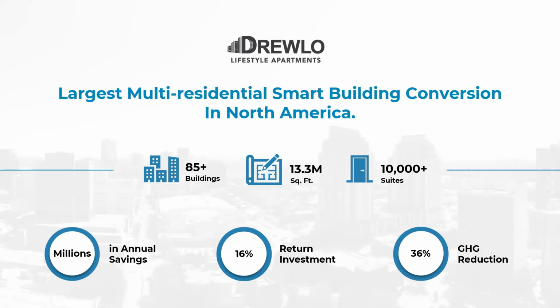That is the optimal way to go, because the old rule of thumb, and here I'll put some real numbers to this, is that it was not uncommon in the past for engineers to size the boiler systems for these multi-res buildings to somewhere between 25 to 30 BTUs per square foot of installed capacity, right? That is a general rule of thumb I've seen in so many buildings, and I'm not saying they were wrong for doing that. Realistically, the buildings never operated at that high level. That number does include some redundancy. Nobody has a building that doesn't have at least one extra spare boiler to compensate for downtime. But it's still too high.